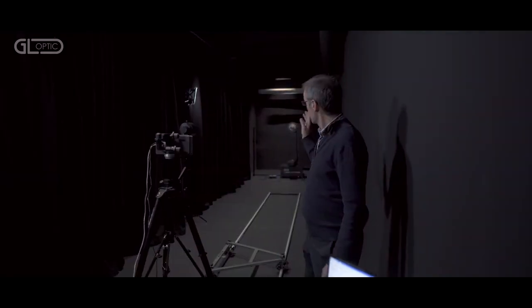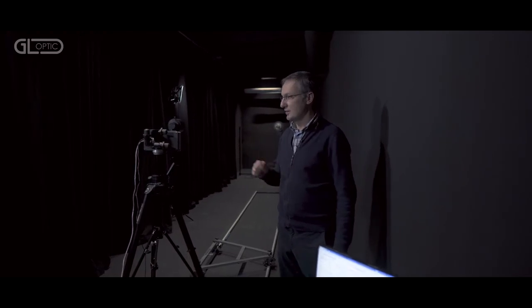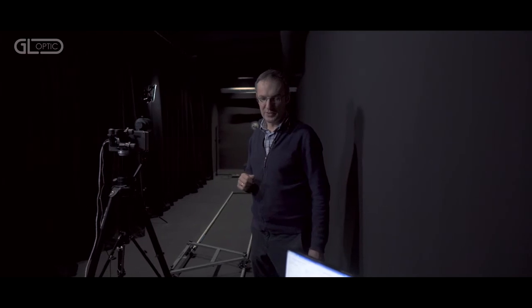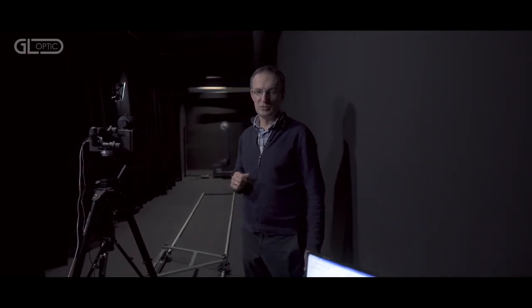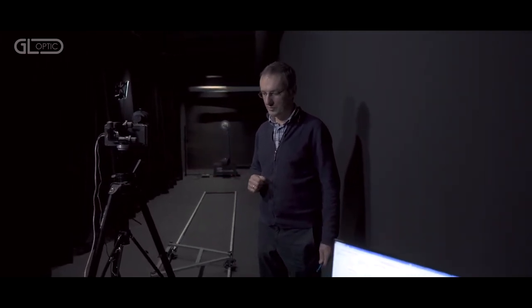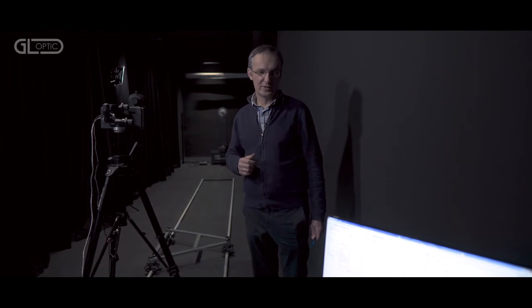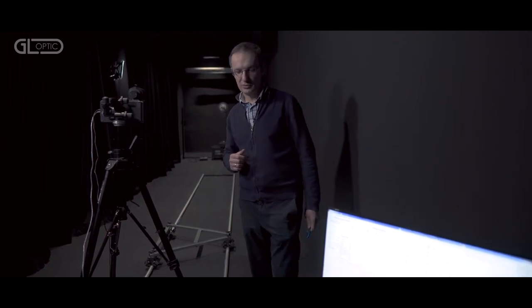The device is positioned on the goniometer. The sensor is set and fixed. We have chosen the spectroradiometer to do the measurements. The position of the spectroradiometer is adjusted and blocked. Now it's time for setting the correct parameters in the software.